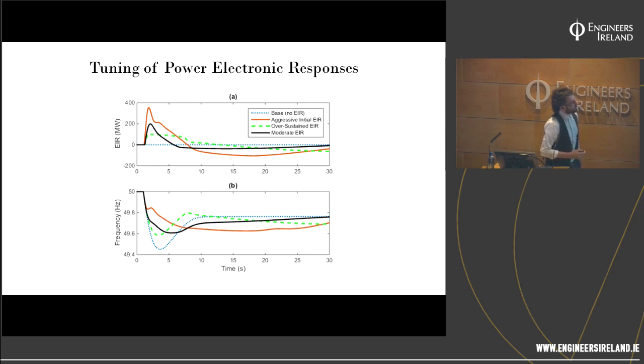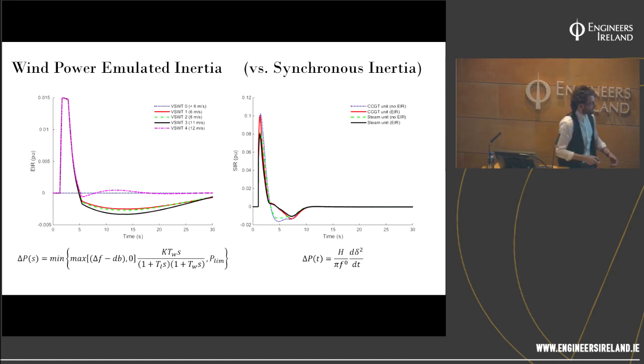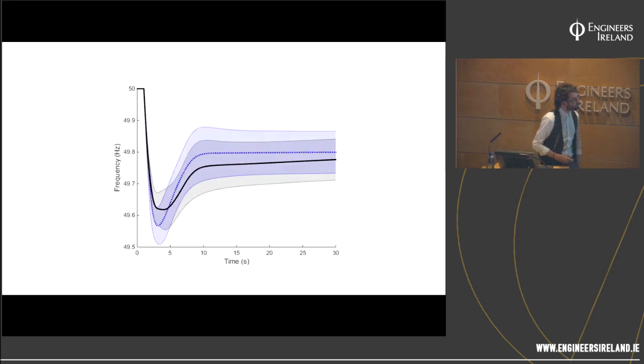So when you get a very aggressive initial response, that red line there, the system frequency nadir, or minimum, is formed. But because you've asked for so much, the recovery is quite great, and the frequency falls again. Likewise, this is the gain of the machine. And you can also control how quickly and how long it responds for with these time constants.